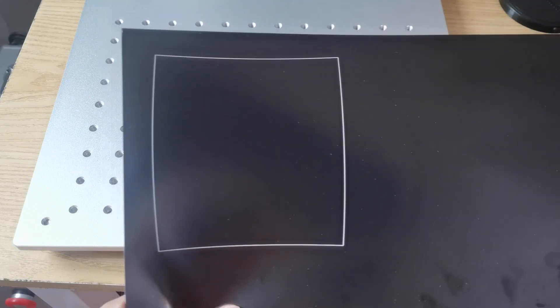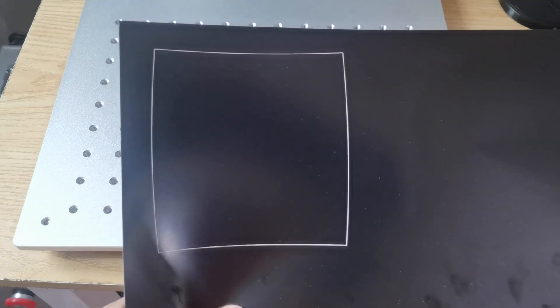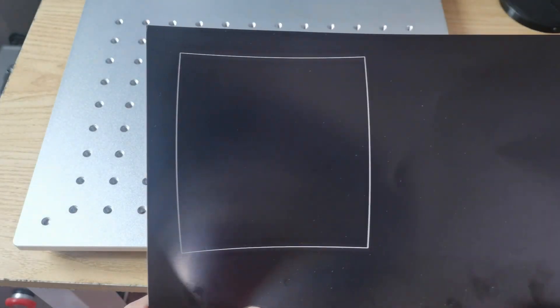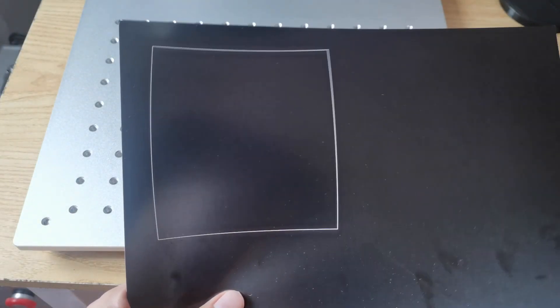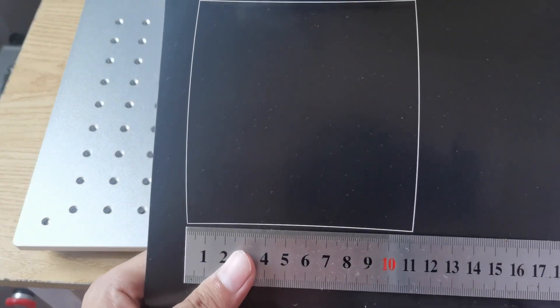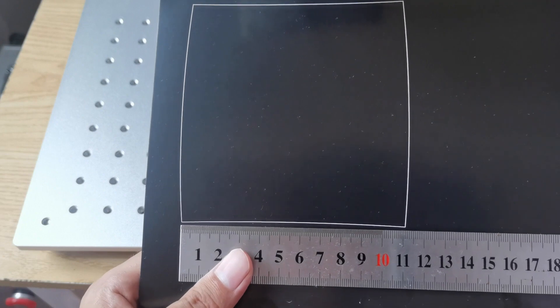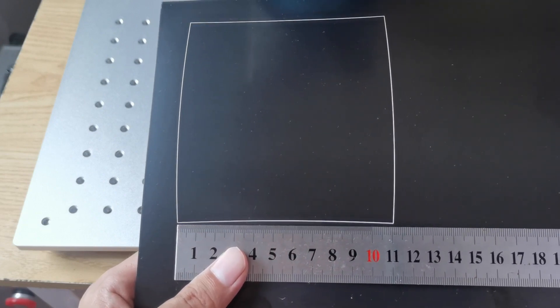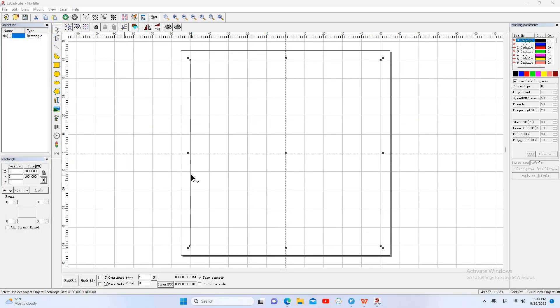We found some problems. First, the lines in our design are straight lines, but the marking lines are not straight. And the size is not correct — it's 110, but our design is 100. We calibrate the galvo head in the software.